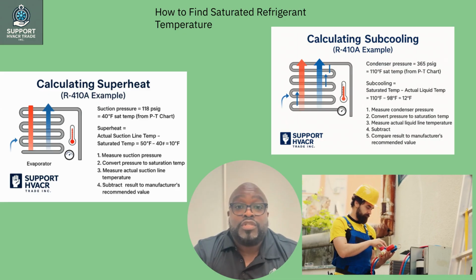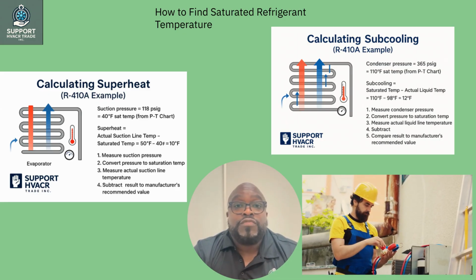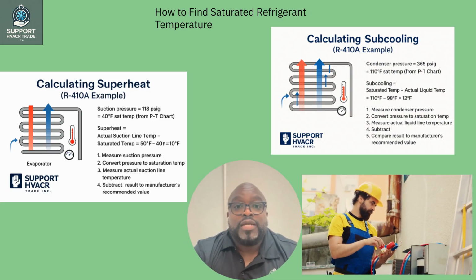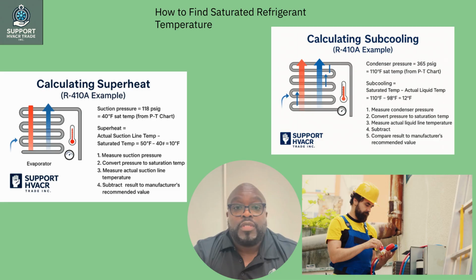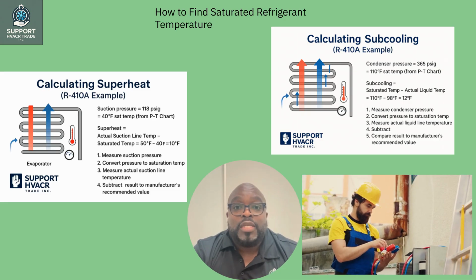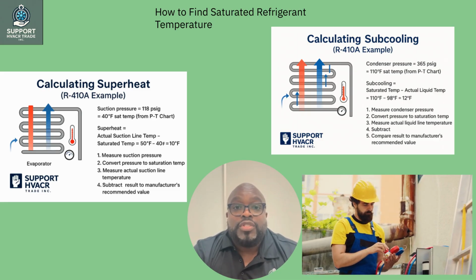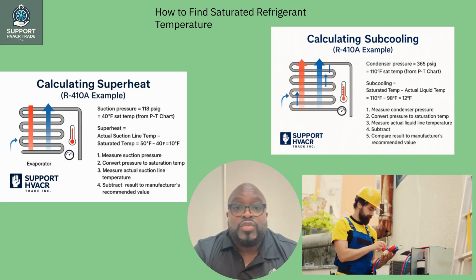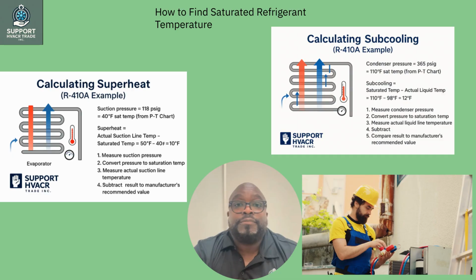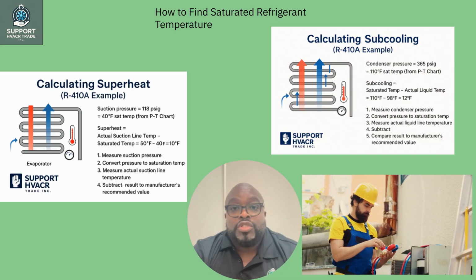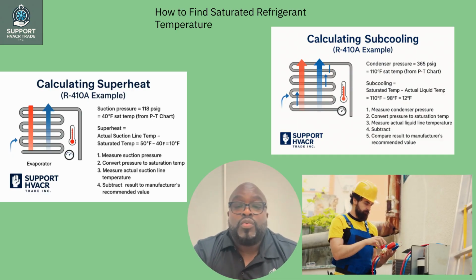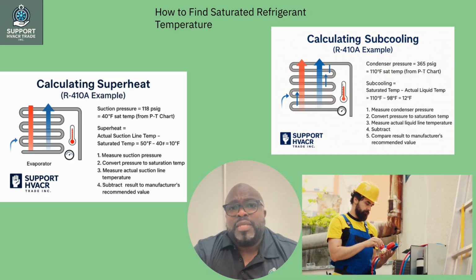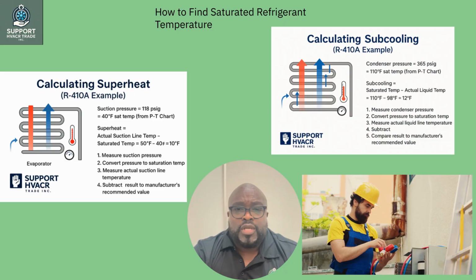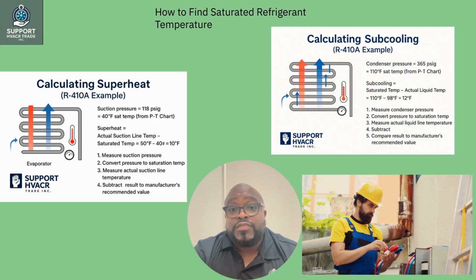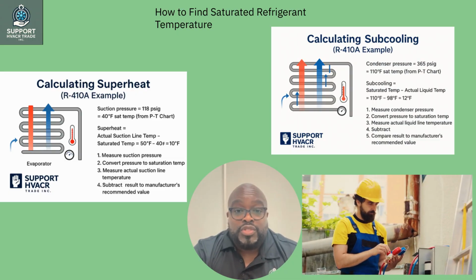Use a pressure temperature PT chart. Every refrigerant, R22, R410A, R134A, etc., has its own PT chart. Find the pressure you measured with your gauge. Look across the chart to find the corresponding saturation temperature. Example: suction pressure on an R410A system equals 118 psi. The PT chart shows that 118 psi equals 40 degrees Fahrenheit saturation temperature.